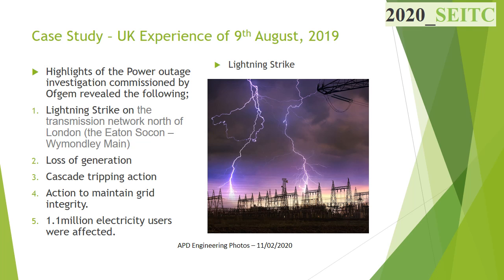1. There was a lightning strike on the transmission network north of London, the Eaton Socon – Wymondley Main, at about 16:52 hours. About 500 megawatts of generation were lost in the first instance from embedded distributed generation. This was closely followed within seconds by a drastic reduction in output by Hornsea Offshore Wind Farm and Little Barford Gas Plant Station. About 1,378 megawatts was lost. The sudden loss of generation caused the frequency to fall quickly and go outside the normal frequency range of 50.5 Hz to 49.5 Hz.